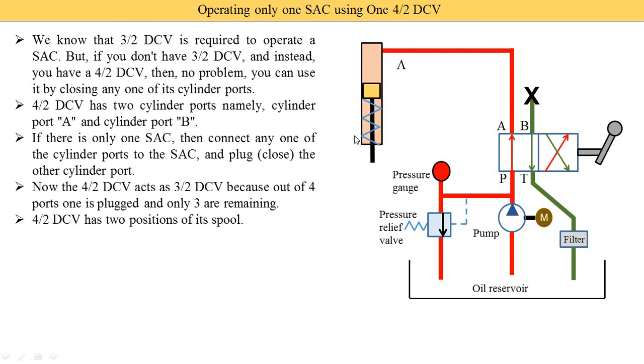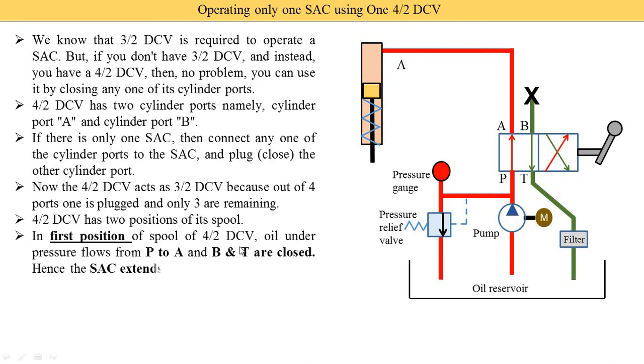Now we understand the first position of the single acting cylinder. In the first position of the spool of the 4/2 DCV, oil under pressure flows from P to A, and B to T are closed. Hence the single acting cylinder is extended. You can see the P port is connected with A — oil comes from the reservoir to the pump, pressurized oil arrives at port P, flows from P to A, enters the single acting cylinder, and the pressurized oil applies force on the piston. Due to this force, the piston starts to move in the downward direction — that means it is called extension.